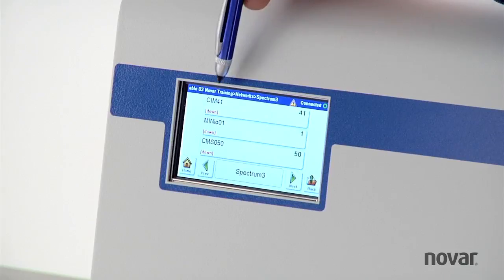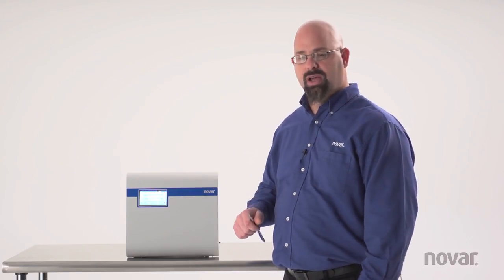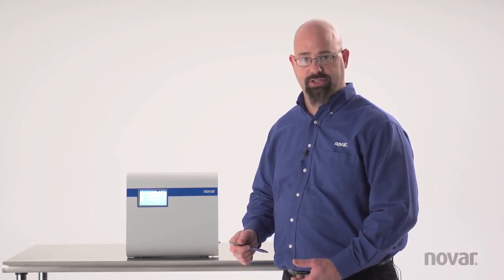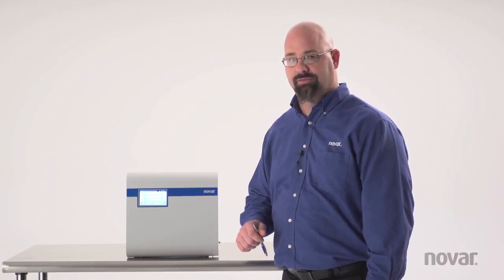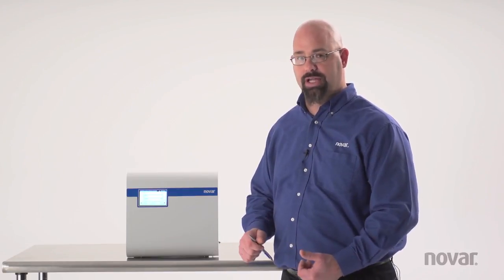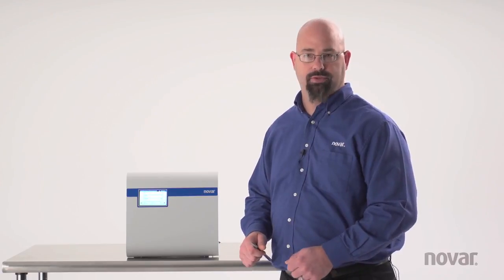In this case I'm going to check the modules for their power and communication voltages, check their addressing to make sure that's correct, come back to the XEM 20R, check the communication voltages on the terminals there with no wires attached, and try to verify and figure out what's wrong with those modules and why they're in comm loss.